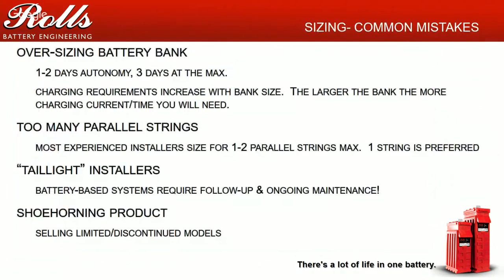Couple issues about sizing. Common sizing mistakes that we see out there. The number one sizing mistake would be oversizing the battery bank. The go big or go home mentality. It's not really the best thing. Typically what you want to do is go to 1 to 2 days of autonomy, 3 days really at the max.